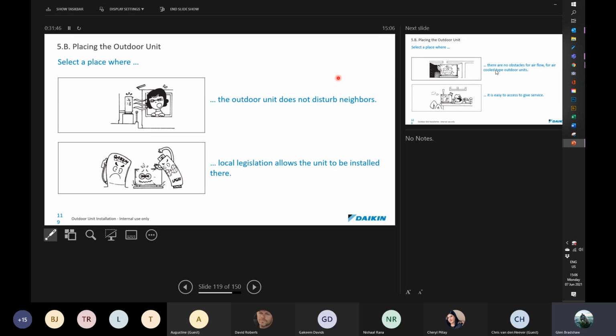Okay, so placing of the outdoor unit. All right, so very important, okay, that the outdoor unit is placed in such a manner that it does not disturb the neighbors. Now, Daikin units are some of the quietest units on the market. Okay, but that does not mean that if you place it outside somebody's window, they're not going to hear it. Okay, so it's very important that that is taken note of, because we don't want units to be waking people up or keeping them up all night. And like I said, they are quiet, but sound has a habit of being amplified depending on the surfaces that it bounces off of as well. And again, that's something that we will discuss in the installation next week.